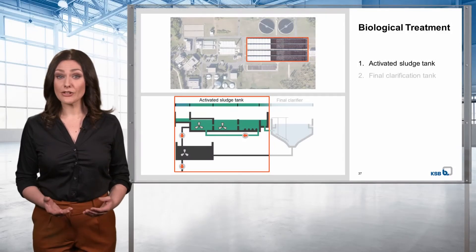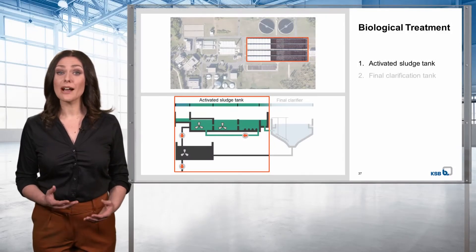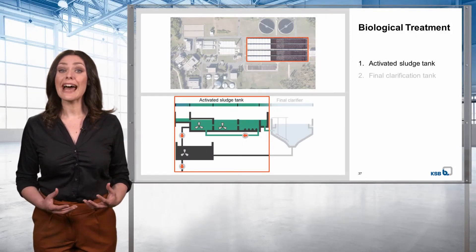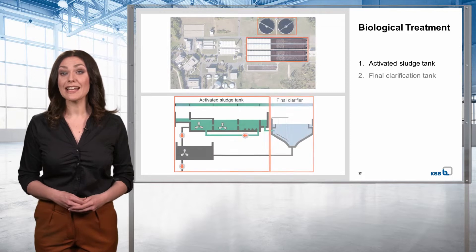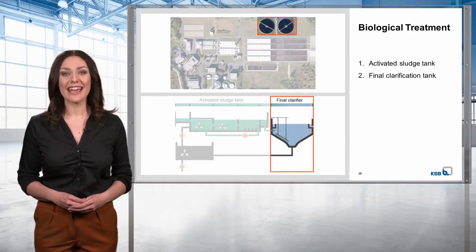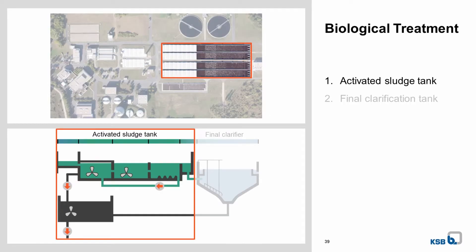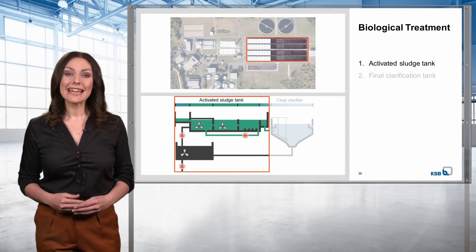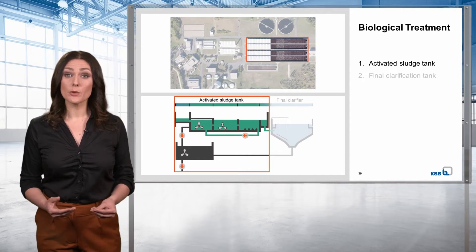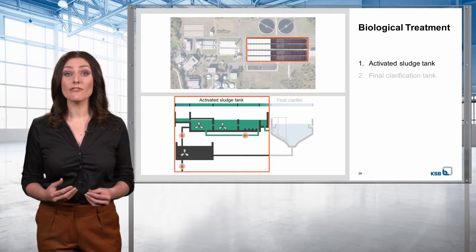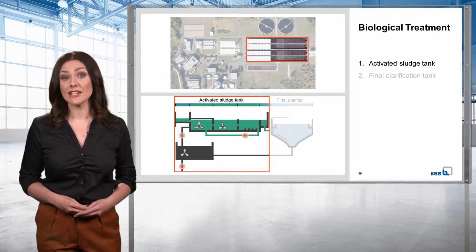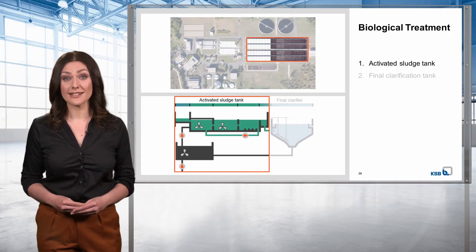The biological treatment stage comprises a so-called activated sludge tank and a final clarification tank. The activated sludge tank is the place of nitrification and denitrification processes. In larger wastewater treatment plants, the additional step of phosphate elimination is carried out before these processes.